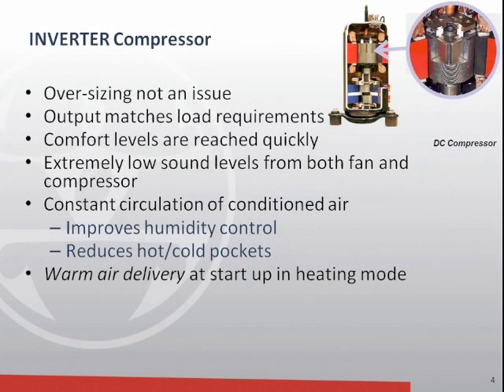You've got a continuously active cold coil on the indoor unit that is able to take moisture out of the air on an ongoing basis. When the outdoor unit and the compressor have throttled down to partial capacity, the indoor fan follows and also throttles back. So you're maintaining a nice cold coil, a nice cold airflow, and you continue to take humidity out of the air, even at small or part loads.